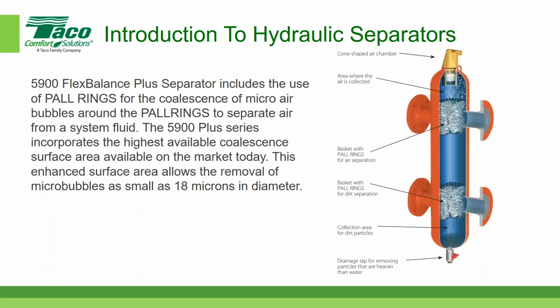Yep. Do you need a minimum amount of straight pipe before the flange size, before entering the air separator? Yes, you should have a minimum of 5 pipe diameters at the inlet and outlet of each of the connections. And that's to ensure uniform flow. The more uniform, the more, what's the word? Laminar. The more laminar the flow is as it enters and leaves the hydraulic separator, the phenomenon of zero pressure drop in the unit itself is accommodated.